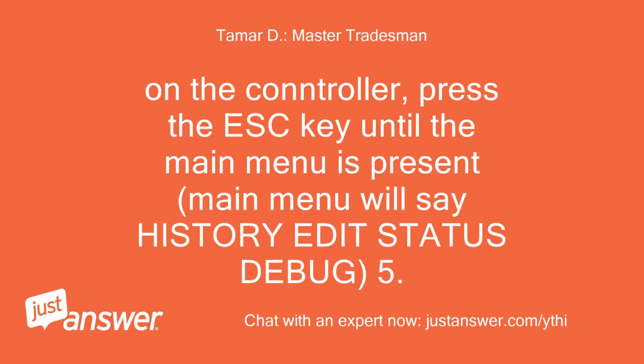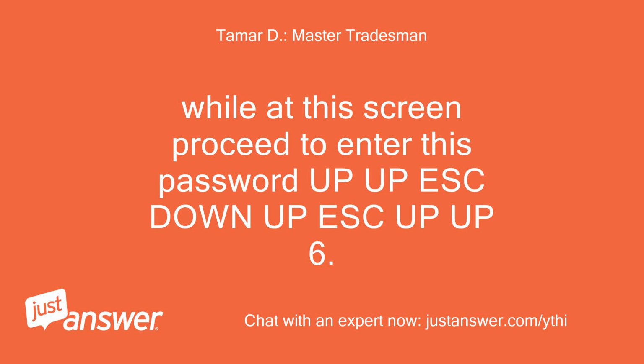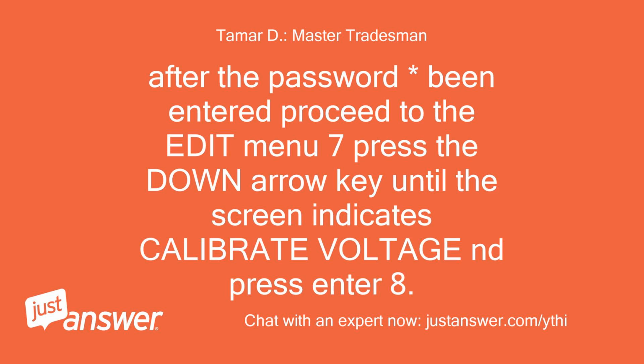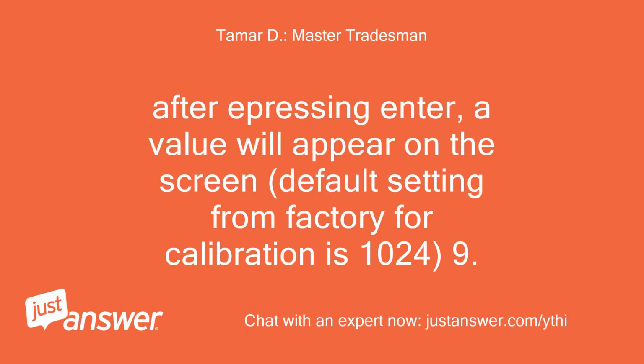4. On the controller, press the escape key until the main menu is present. The main menu will say history, edit, status, debug. 5. While at this screen, enter this password: up, escape, down, escape, up. 6. After the password has been entered, proceed to the edit menu. 7. Press the down arrow key until the screen indicates calibrate voltage. Press enter. 8. After pressing enter, a value will appear on the screen. The factory default setting for calibration is 1024.